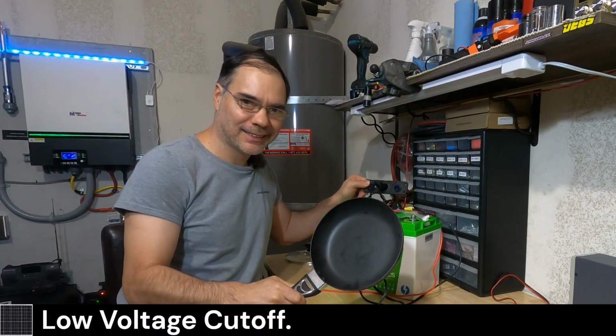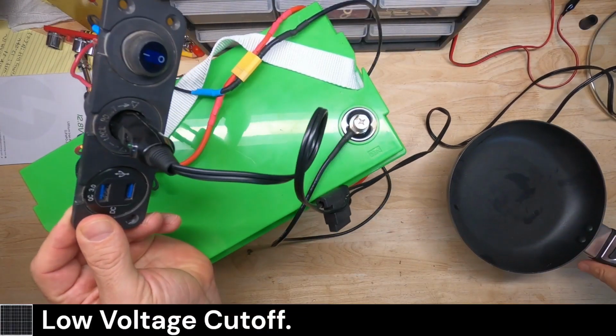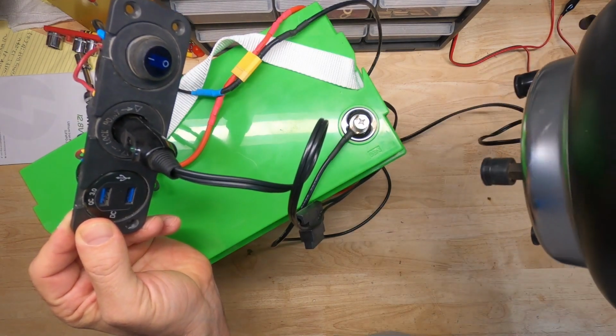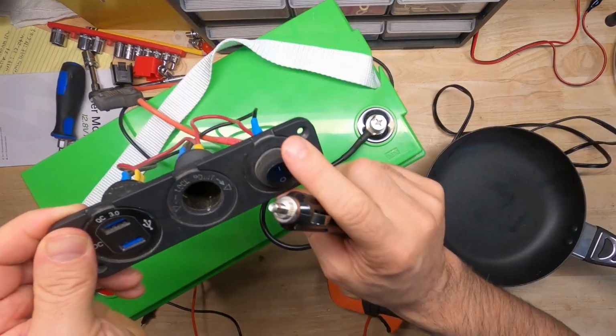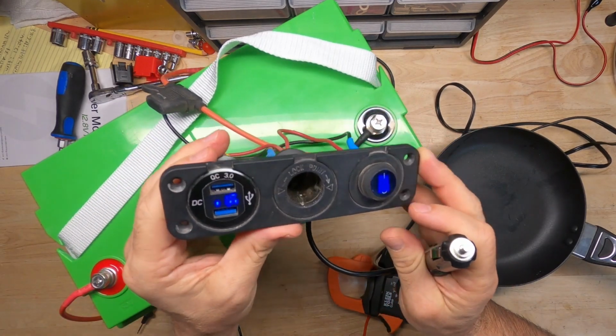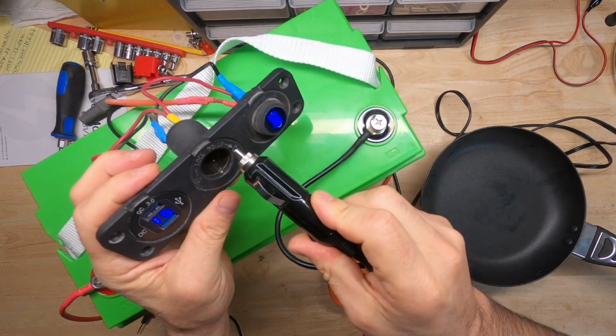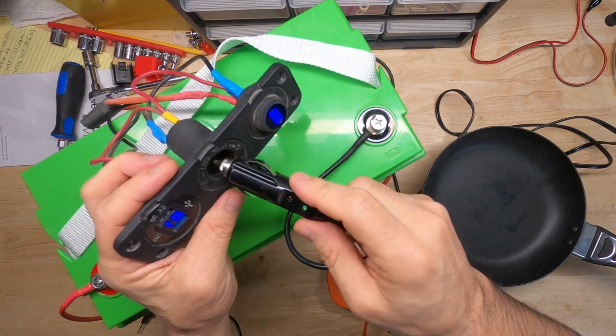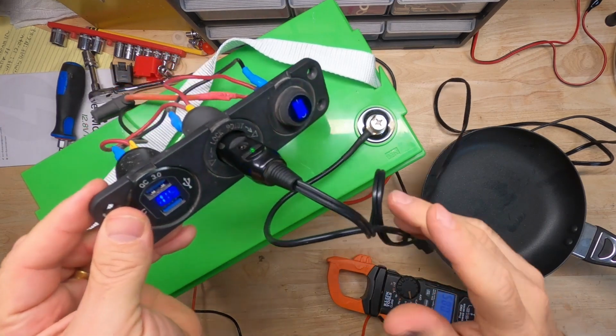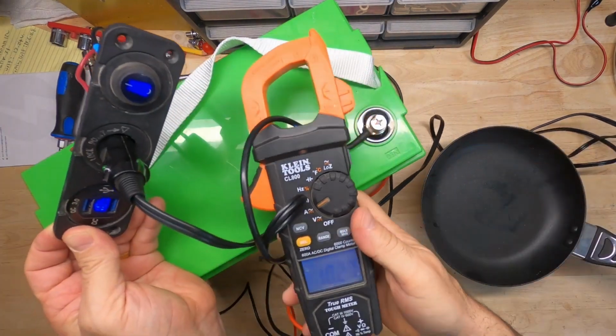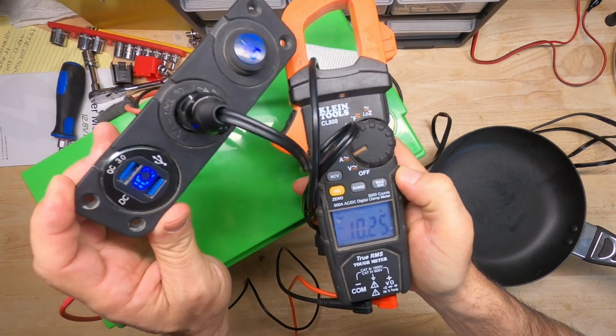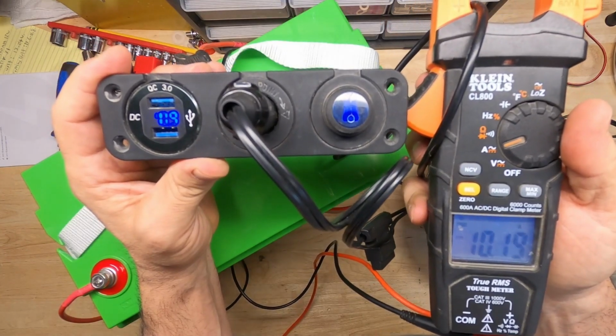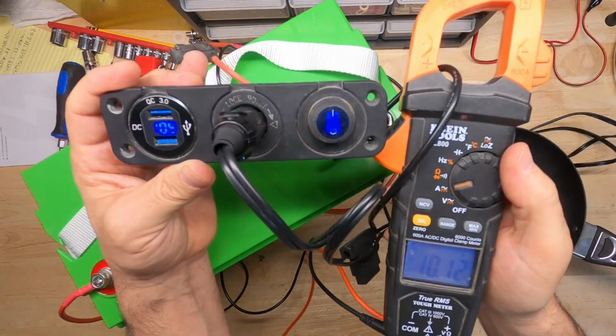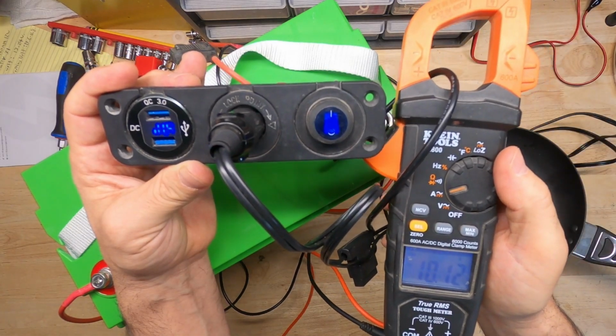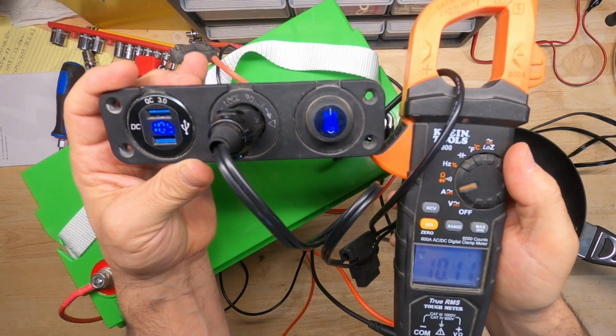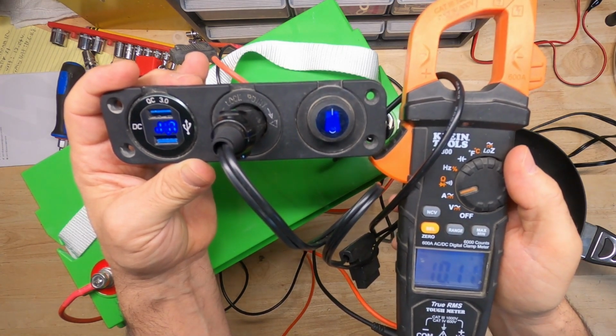The saucepan is back. Alright, you guys may have remembered this from the past. It's crude, but it works. And this will definitely drain the battery to the bitter end. So we'll turn it on here and we'll see what the voltage is going to be. It's 11.6 at rest. Now we're going to plug in our load. This draws about 10 amps. Okay, see the voltage drop to 10.9. We're pulling 10 amps. So if you have an inverter and you forget to turn off your loads, the BMS will protect the battery from going too low in voltage.